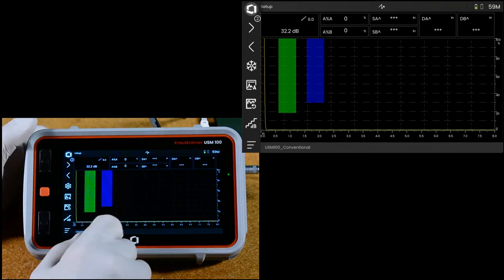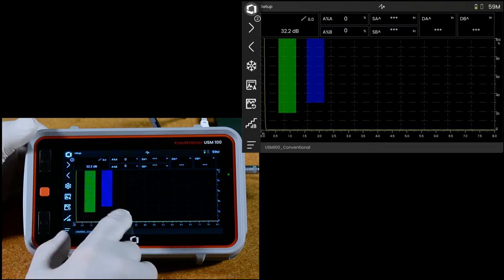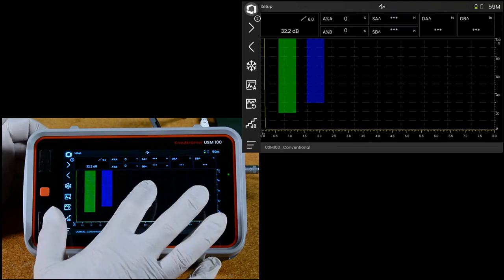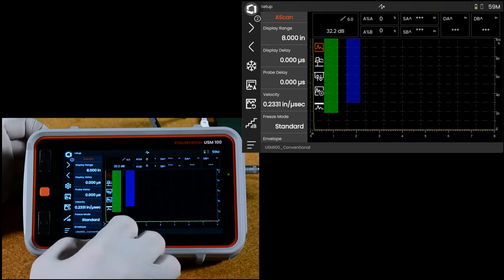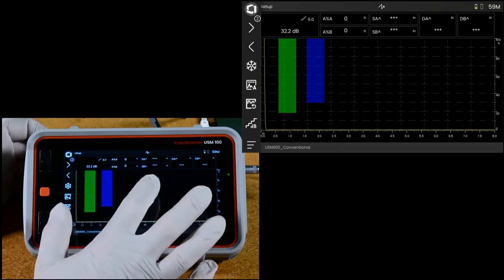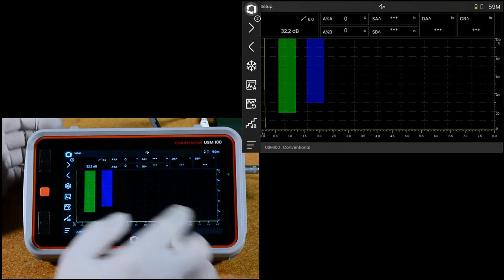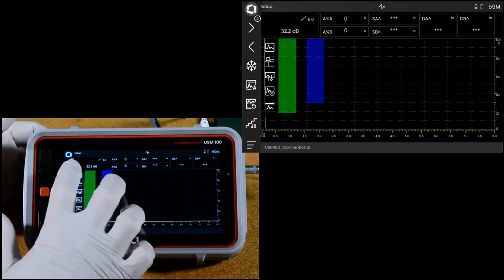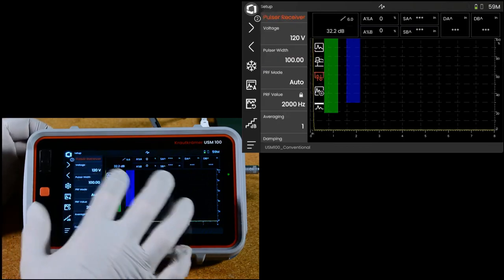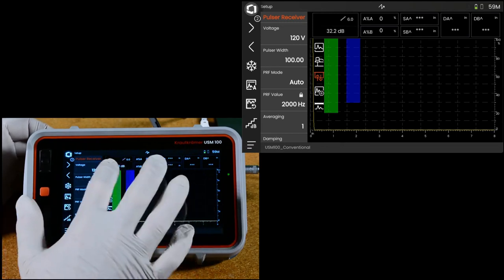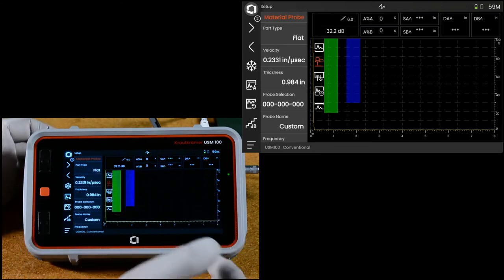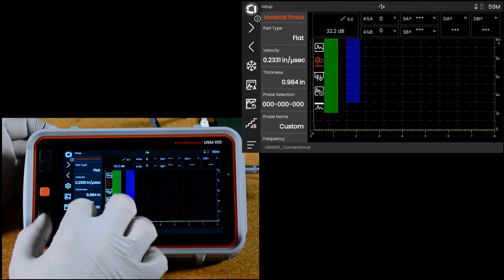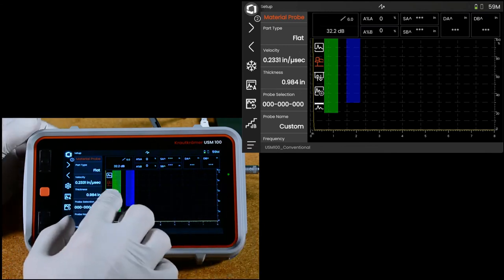Now, various data views also have menus that are specific to them. In the case of the A-scan, we access the A-scan menus by tapping the A-scan and we see menu buttons appear on the left edge of the A-scan. If I close that, tap the A-scan, the menu buttons appear. They only appear for about 2 seconds. But if you tap, select one of them, now the menus stay up for longer. They'll stay up for as long as the menu is open. Going top to bottom, we have A-scan menu. Next one down is probe and material. So, these are all parameters that describe the material that you're inspecting and the probe itself.